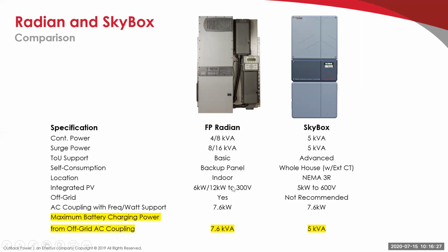Whereas the Flex Power Radian with these charge controllers takes 300-volt strings. But each of these charge controllers can take 7 kilowatts worth of PV. This slide is actually a little outdated. It says 6 or 12, but it should say 7 or 14 kilowatts of PV, because each charge controller can take up to 7 kW of PV. Off-grid, like I said, the Radian for sure. The Skybox is not recommended. If someone is going to go off-grid with Outback equipment, we definitely recommend the Radian.